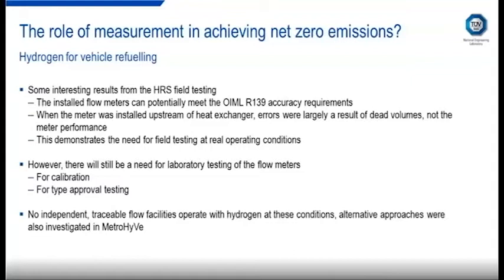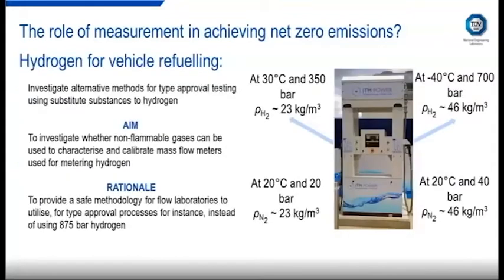So you might have to do this if you're going to calibrate the flow meter before it's installed, or for type approval testing. And there isn't really any easy way to do this right now, because there are no independent traceable flow facilities that can operate with hydrogen at 700 bar and minus 40 degrees C. These facilities just don't exist right now. So we need to look at alternatives. And that's something that was considered in the MetroHyVe project. So we looked at alternative calibration methods using nitrogen and air.